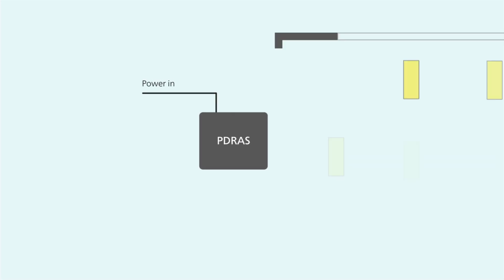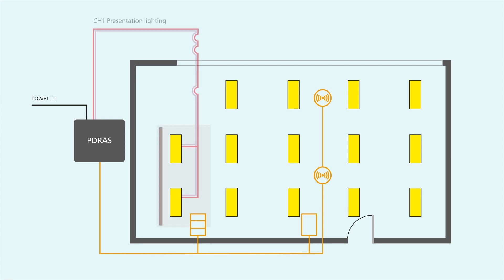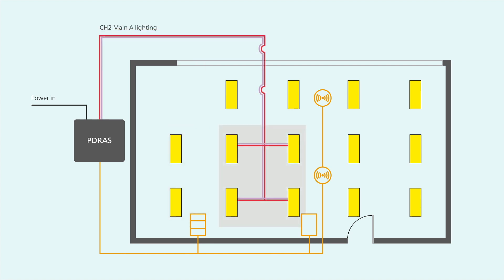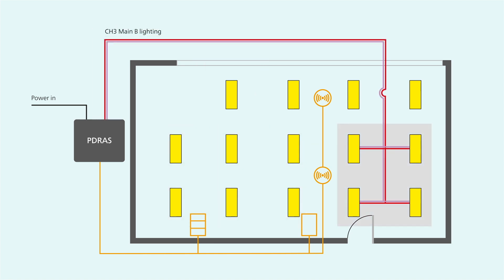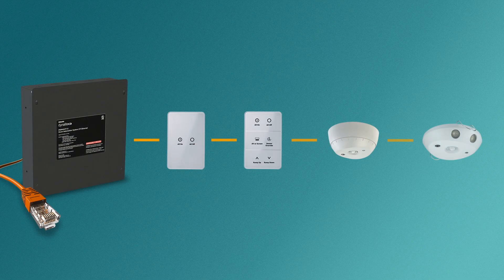One controller supports up to four sensors and/or four wall switches with easy plug-and-play connections. Each controller can accommodate up to five lighting zones — from presentation lighting to general room lighting zones, to window lighting zones, and your plug-load zone. All components are daisy-chained using plug-and-play RJ45 connections for hassle-free installation. The network devices can be connected in any order.